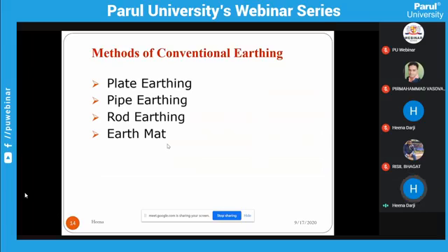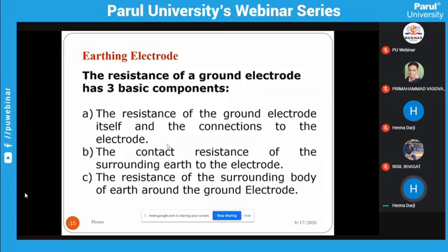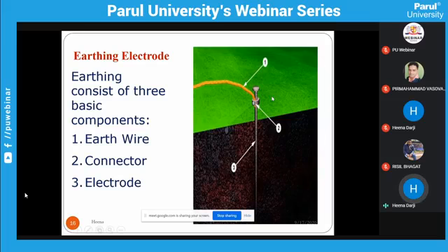Now, there are different types of earthing we use in all places: plate earthing, pipe earthing, rod earthing, and earth mat. The resistance of a ground electrode has three basic components: the resistance of the ground electrode itself and the connection to the electrode, the contact resistance of the surrounding earth to the electrode, and the resistance of the surrounding body of earth around the ground electrode. Now, this is an earthing electrode. How to place the earthing electrode? Earthing consists of three basic components: this is the earth wire, this is a connector, and this is an electrode.